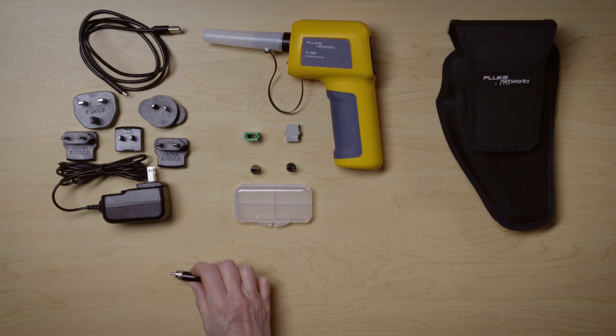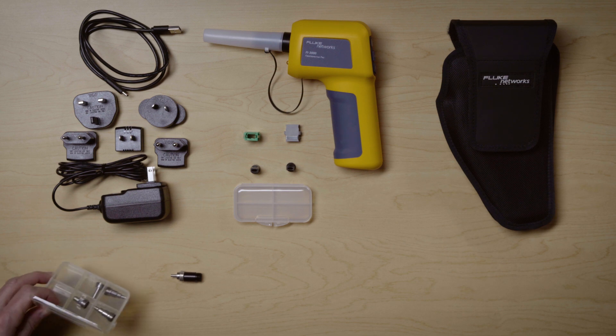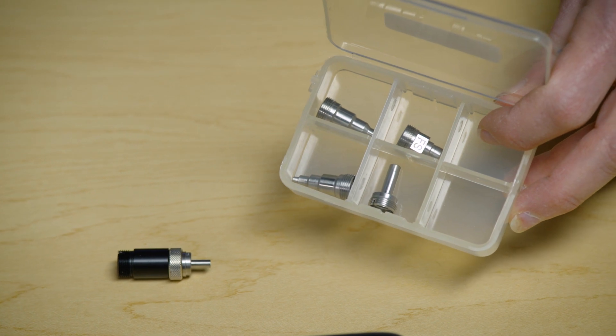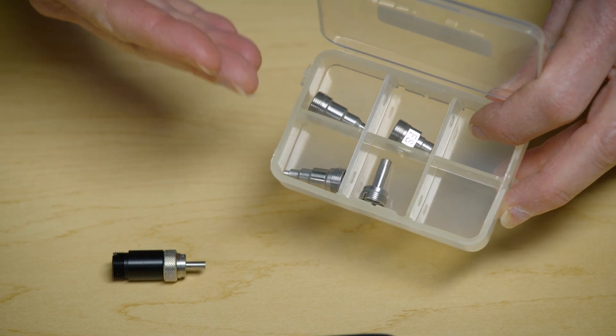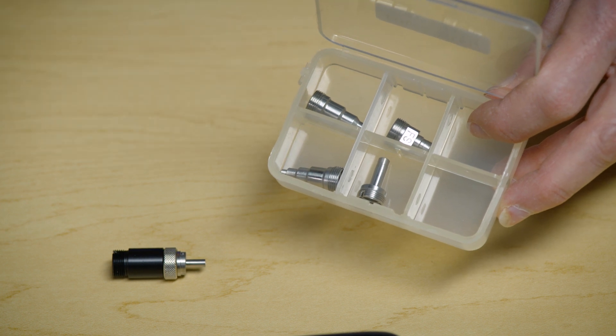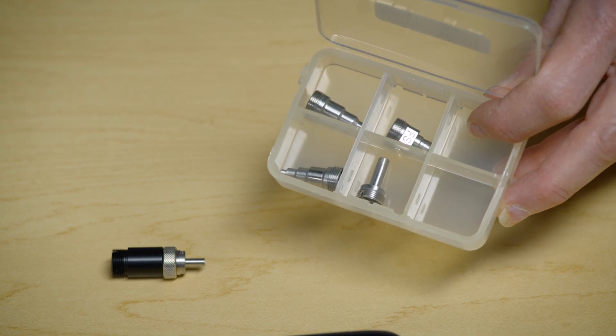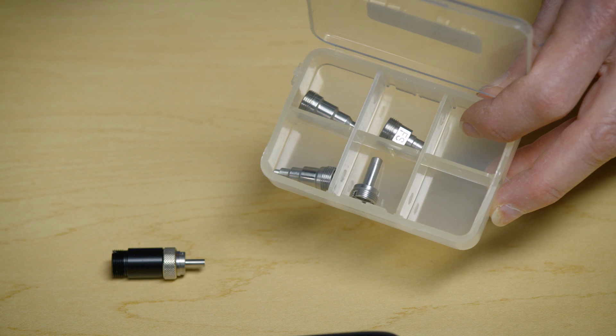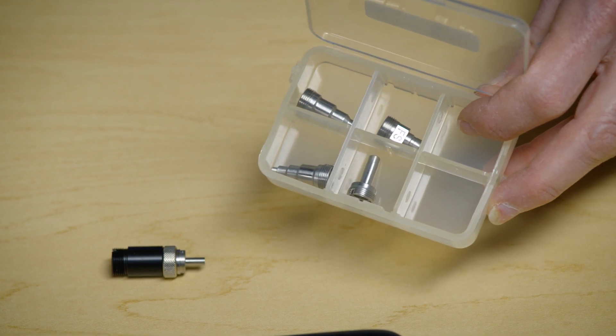The kit also contains this special single fiber adapter which supports a whole range of optional single fiber tips such as these 1.25 and 2.5 millimeter bulkhead and patch cord tips plus a whole range of other tips including an extension tip to get into those hard to reach spaces.